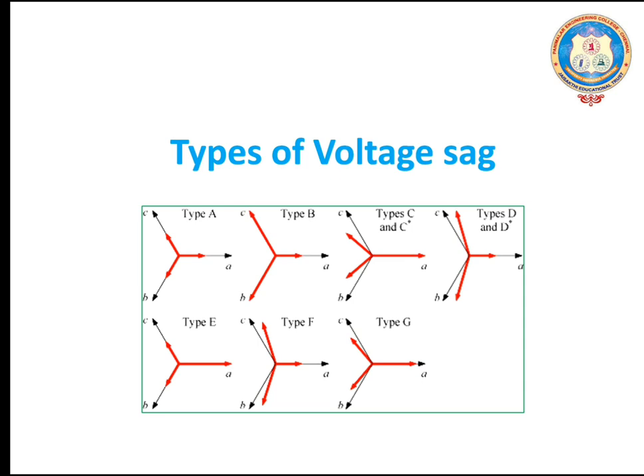In type A, all the phases are in phase and voltage sag occurs in all the phases. In type B, voltage sag occurs in one phase and there is no phase shift. In type C, voltage sag occurs in two phases. In type D, voltage sag occurs and the voltage phase shift occurs in two phases. In type E, voltage sag occurs in two phases but there is no phase shift. In type F, voltage sag occurs in one phase and there are two phase shifts. In type G, voltage sag occurs in two phases and two phase shifts occur.